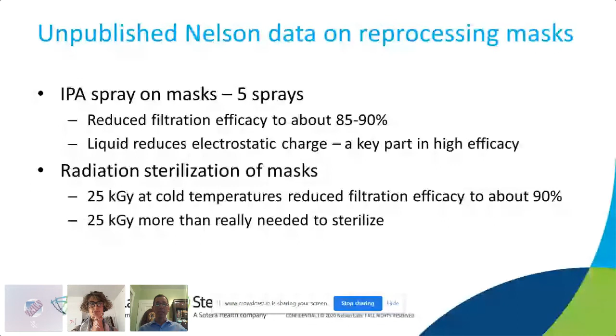We did some work with radiation. We have a large number of irradiators around the world. So we tried 25 kilogray, a standard radiation process, at cold temperatures. And we found that a single dose of 25 kilogray at cold temperature reduced the efficacy from 95% to about 90%. We do not have exhaustive data yet, like how many times you could do that. But 25 kilogray is really more than you would need to meet the criteria that FDA has established. We just shot at that dose to get an initial feeling for how things looked.